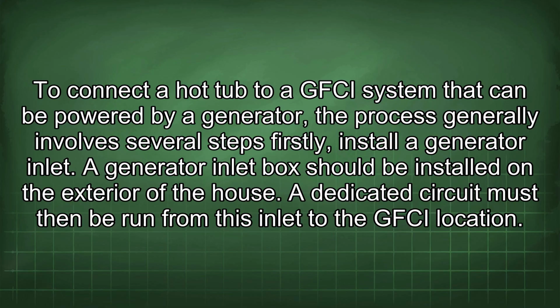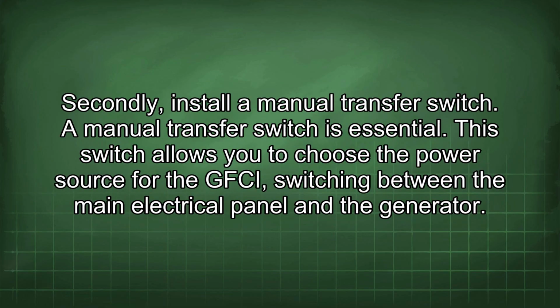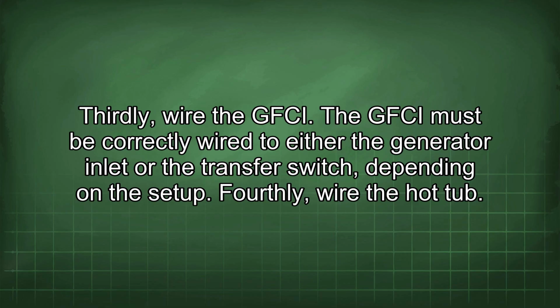generally involves several steps. Firstly, install a generator inlet. A generator inlet box should be installed on the exterior of the house. A dedicated circuit must then be run from this inlet to the GFCI location. Secondly, install a manual transfer switch. A manual transfer switch is essential. This switch allows you to choose the power source for the GFCI, switching between the main electrical panel and the generator. Thirdly, wire the GFCI. The GFCI must be correctly wired to either the generator inlet or the transfer switch, depending on the setup.